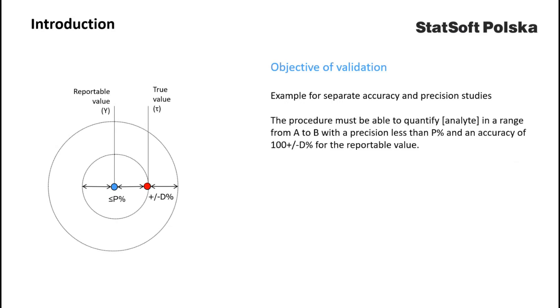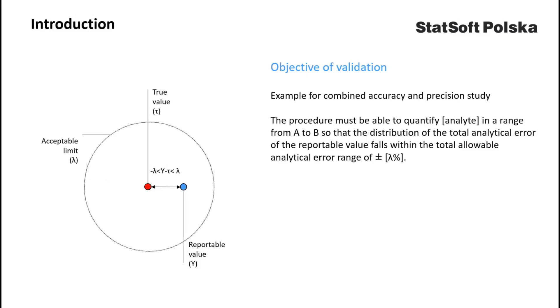In the case of separate accuracy and precision studies, the objective of validation may be defined as follows: the procedure must be able to quantify the analyte in a range from A to B with precision less than a predetermined limit and with accuracy within the predetermined range of the reportable value. In the case of a combined accuracy and precision study, the objective may be that the distribution of the total analytic error of the reportable value falls within the total allowable analytical error range.